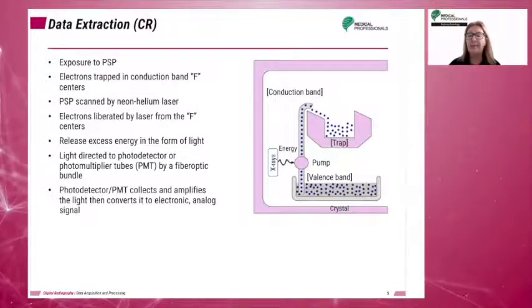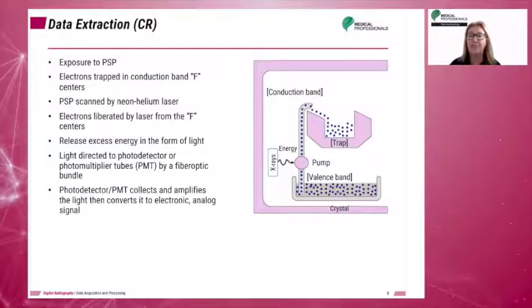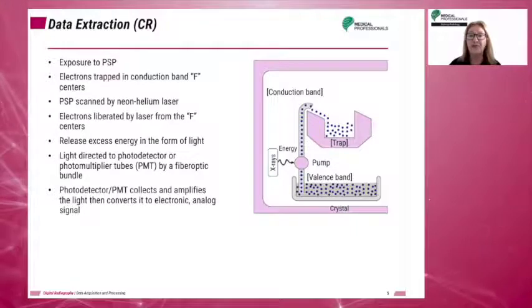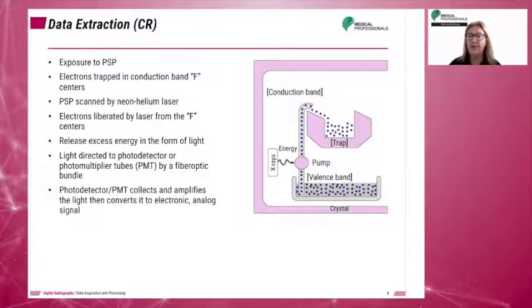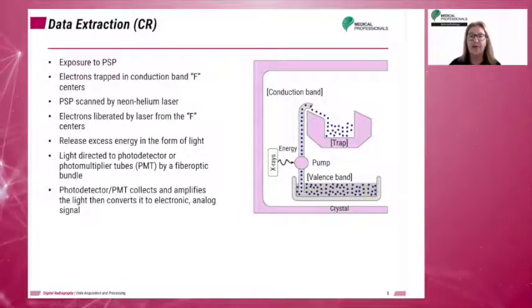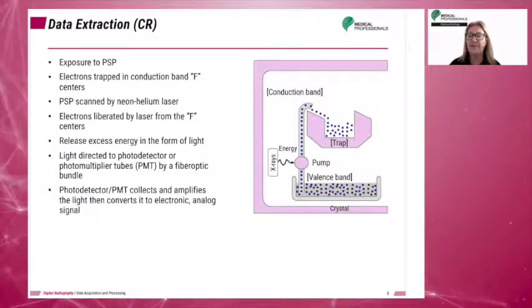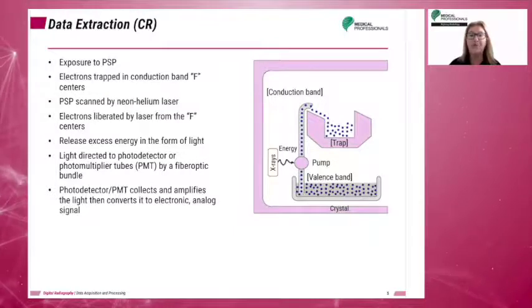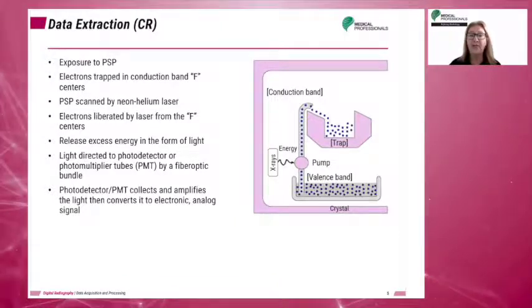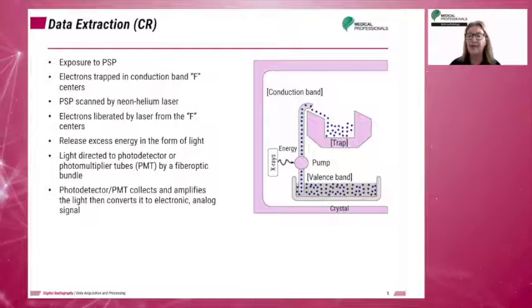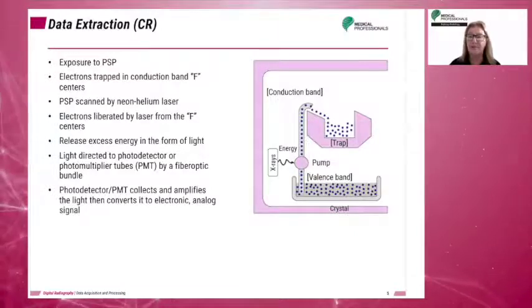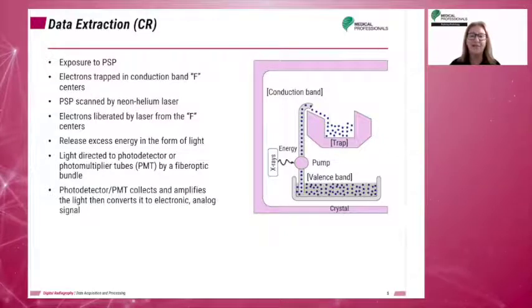These trapped electrons are the latent image. The PSP is scanned by the laser in the plate scanner, which liberates the trapped electrons. As the electrons return to their shells in the phosphor atoms, they release energy in the form of light. The light released is directed to a photodetector by a fiber-optic bundle, where it is amplified and converted to an electrical or analog signal. The magnitude of the electrical signal is directly proportional to the intensity of the remnant beam.